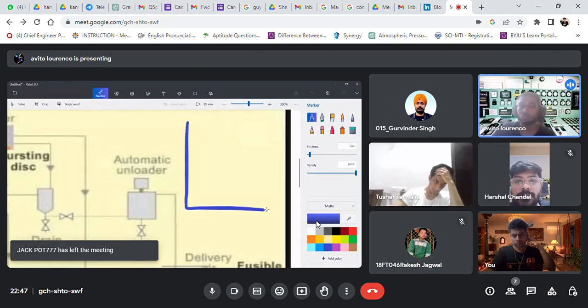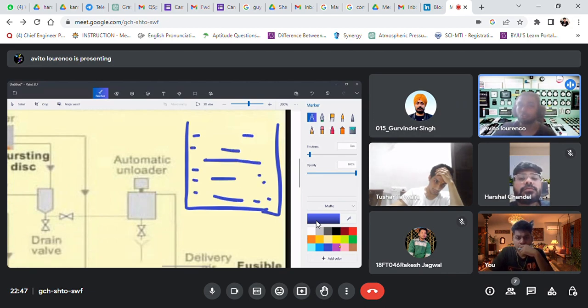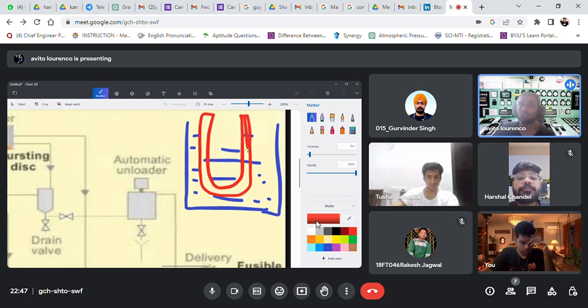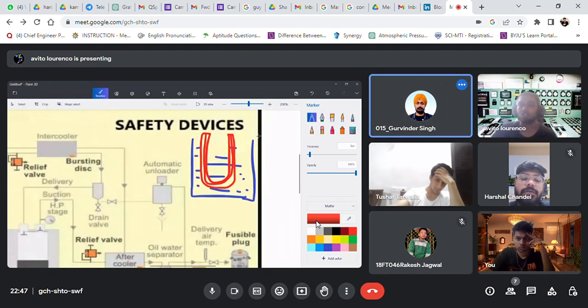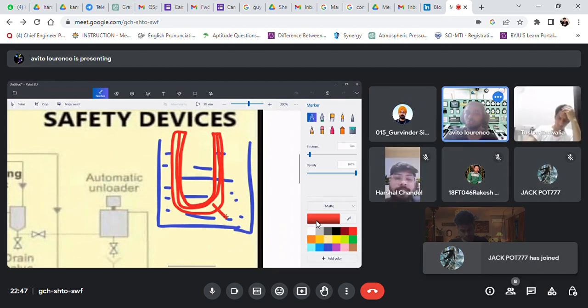So this is the water. There is just plain water inside, coming in and going out. And inside this is super high pressure compared to the water. Water is hardly 1 to 2 bar. Inside this is pressurized air, 5 bar. So how will this water get highly pressurized enough to break this? Only if this has a leak.